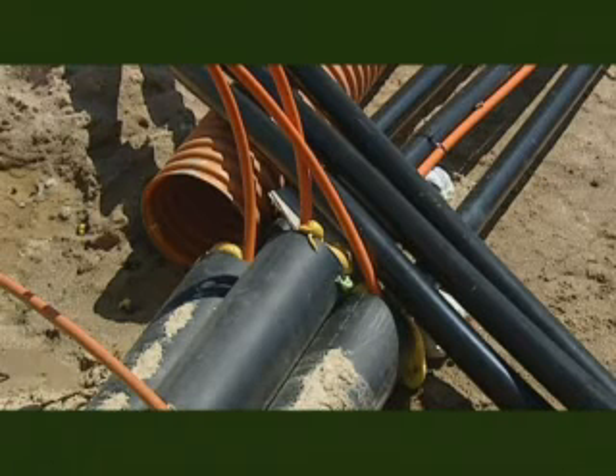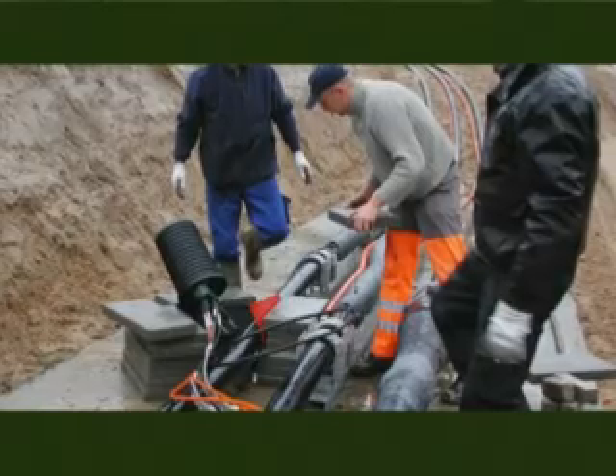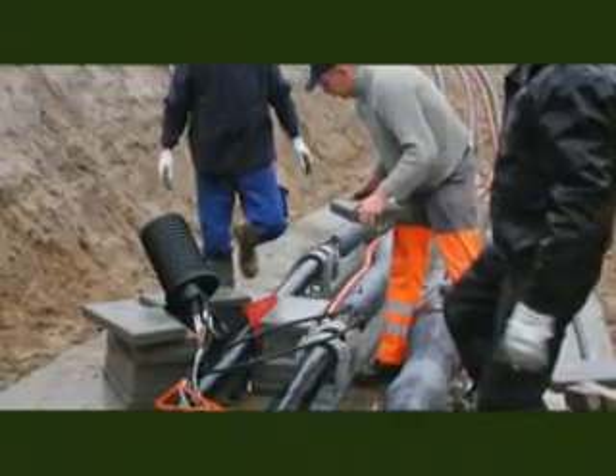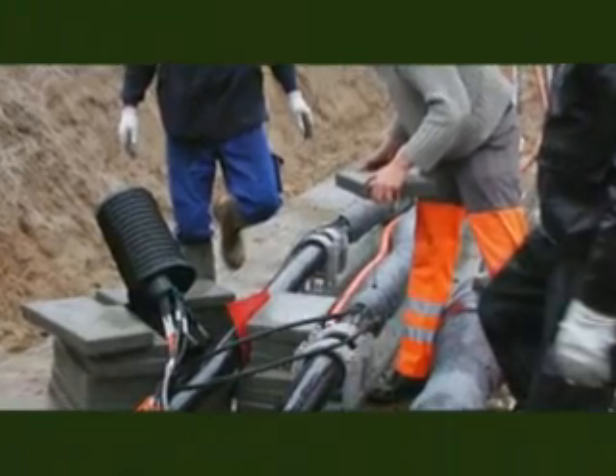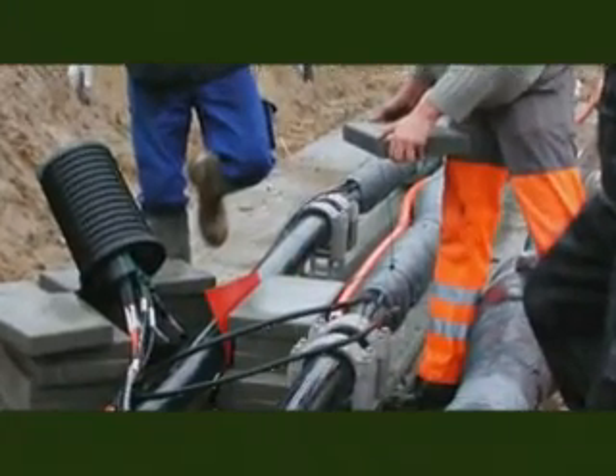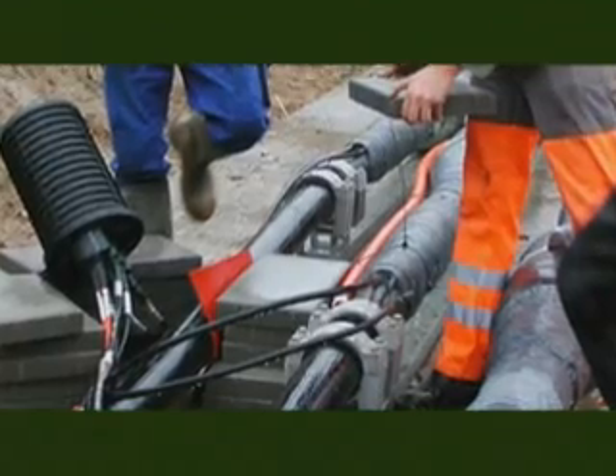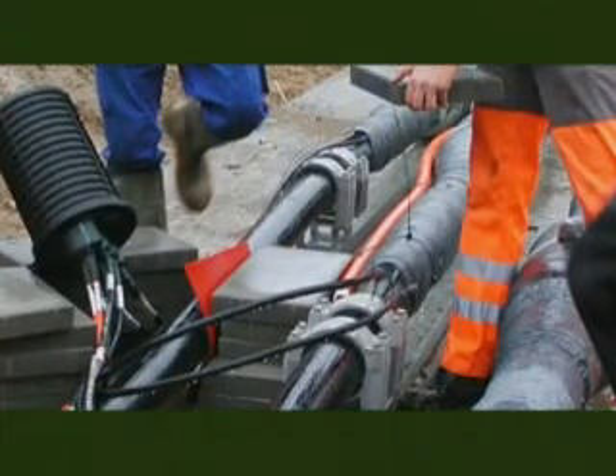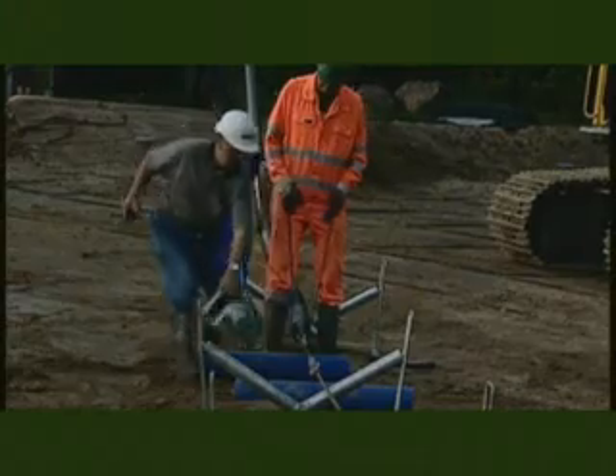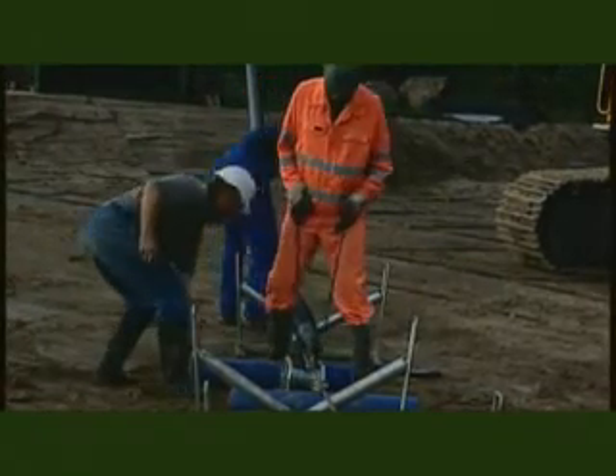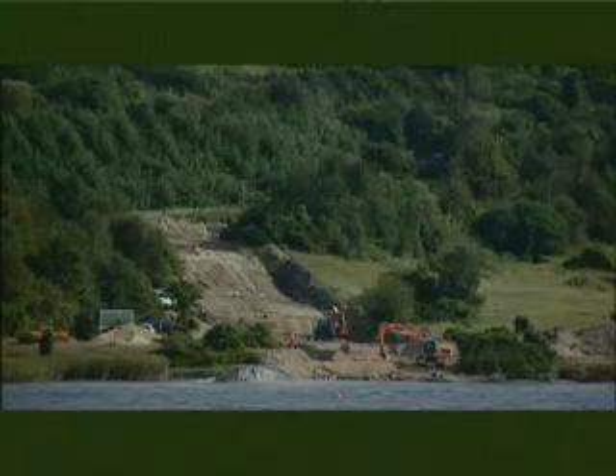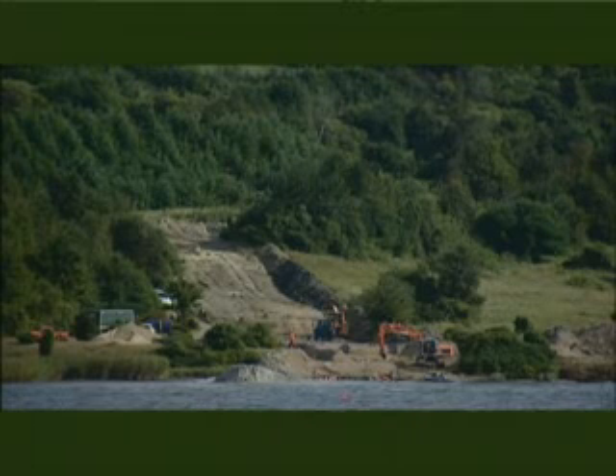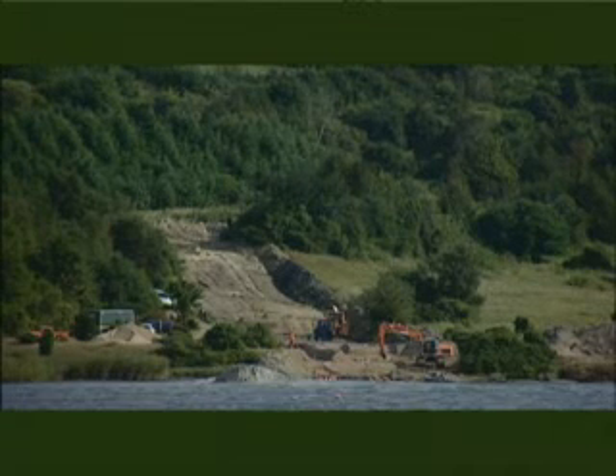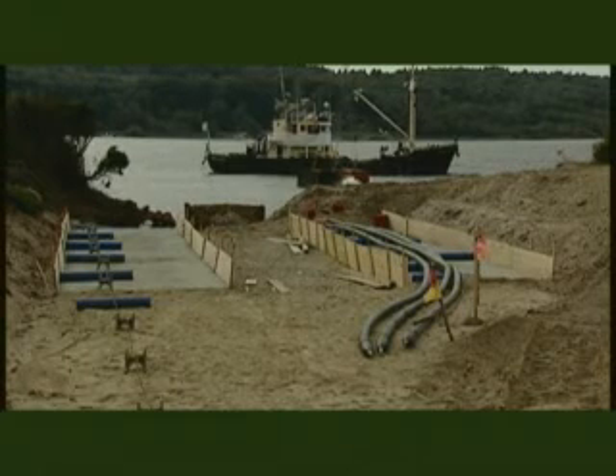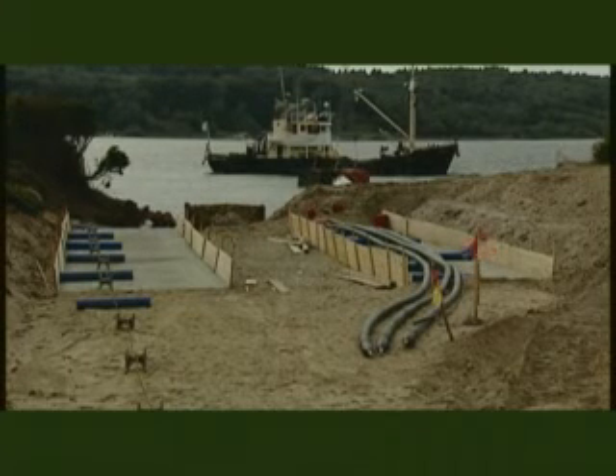Empty pipes for fibre optic cables have been laid alongside the land cables. Once the system was established, fibre optic cables were flushed into the pipes. They serve 2 purposes. They're partly used for communications, and they can also be used for distributed temperature monitoring along the cables. The submarine cables were supplied with fibre optic cables built into the shield. At joints numbers 1 and 2, at the transition between land and submarine cable, the built-in fibre optic cables are spliced together with the conventional fibre optic cables, which are laid in plastic pipes.